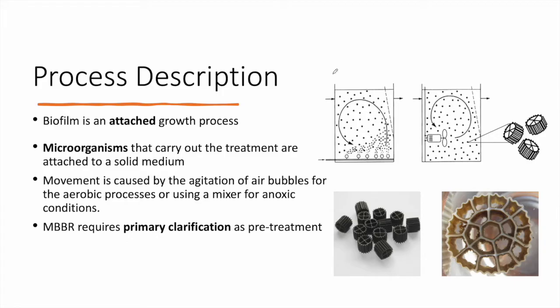The MBBR is a secondary treatment. The primary treatment is usually a clarifier where particles settle down, forming sludge, with significant removal of total suspended solids and some reduction of BOD. The wastewater is then transferred into the secondary treatment, which in this case is the MBBR. The MBBR can consist of many reactors, whether aerobic, anaerobic, or anoxic.